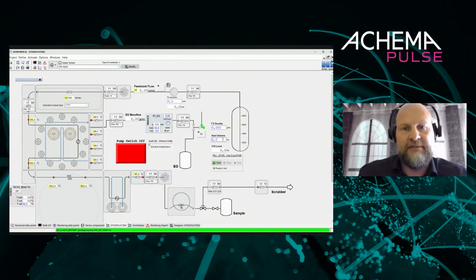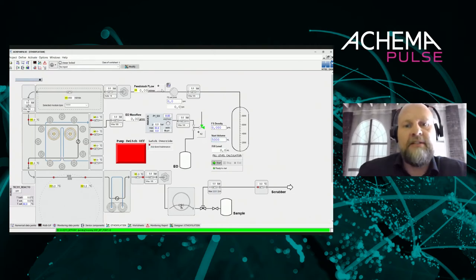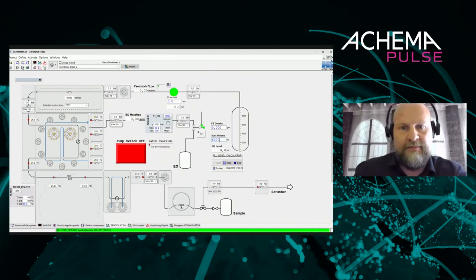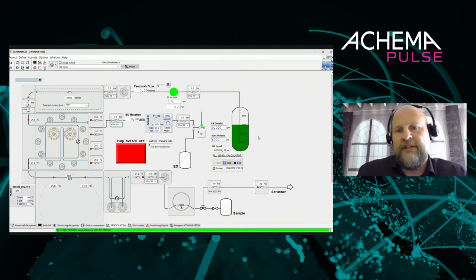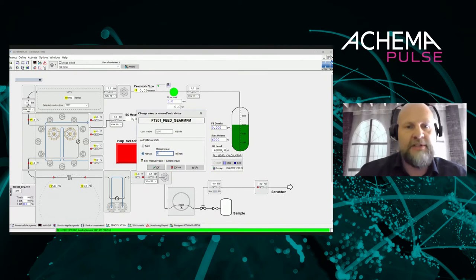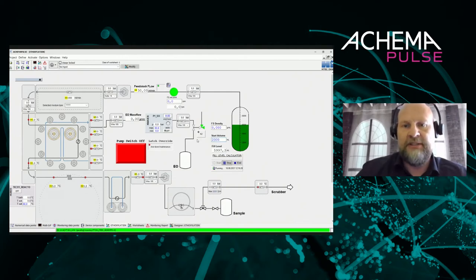Because there wasn't time to install a proper level measurement on the feedstock vessel, we programmed a kind of estimation for fill levels. When the feedstock pump starts, a program calculates the feed level according to the actual measured flow. This gives a sort of countdown estimate of the remaining material. Color-coded warnings appear when you reach a certain level.